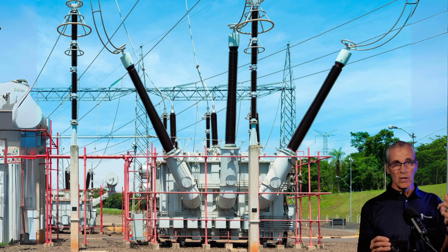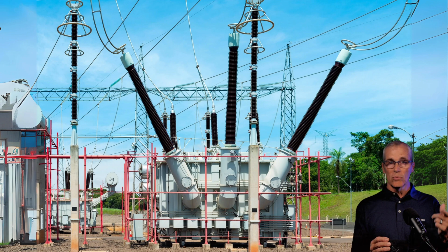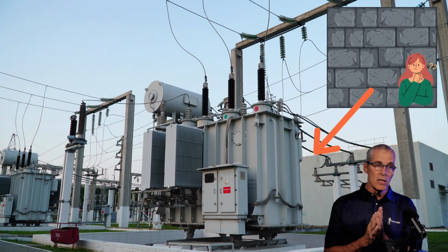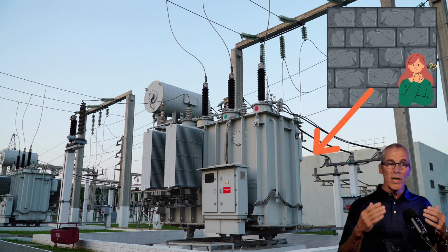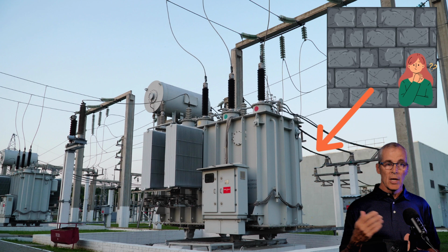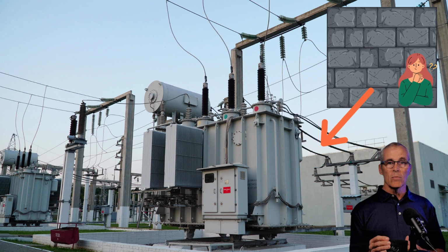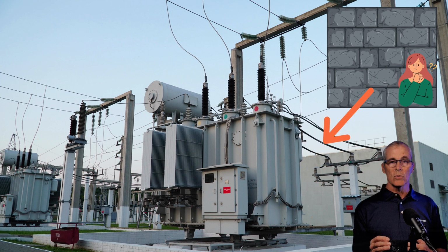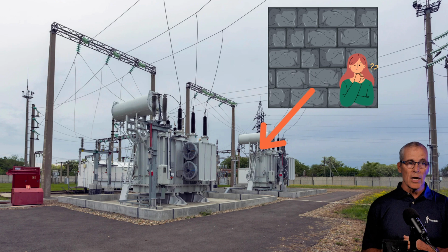In fact, if this one fails, there are cases where you don't want this water spray system operating, especially if it could spread the oil, make the fire worse. In this case, should there be a firewall between these two locations? There's a transformer. You can see there's a containment pit. There's a nearby building, and we don't know really what that building is, service building, switchgear building. We'll answer that question.